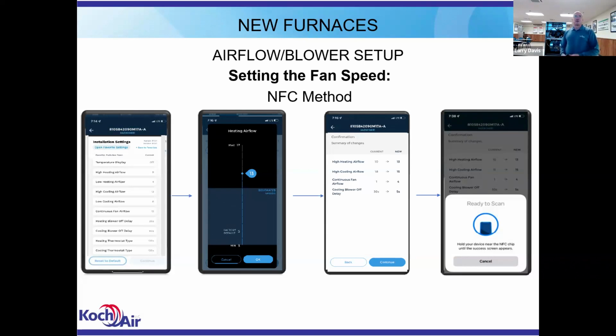Okay. So on the first image on the left, you can see that it has the furnace model and serial number at the top. You're going to check that. That's the information in the board. Check it with the label on the unit. Make sure a board hasn't gotten swapped with another furnace. Okay. If you do have to swap a board, we can talk about that here in a minute. You can reprogram a board. Okay. So, but we'll talk about that on board replacement.